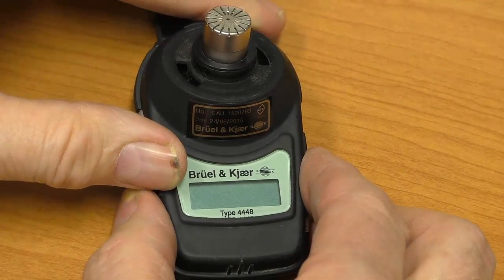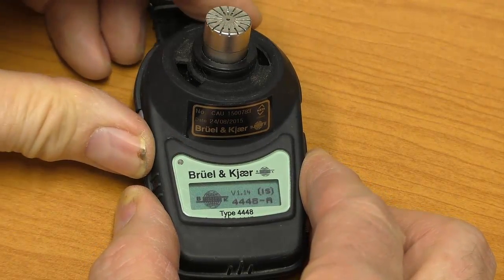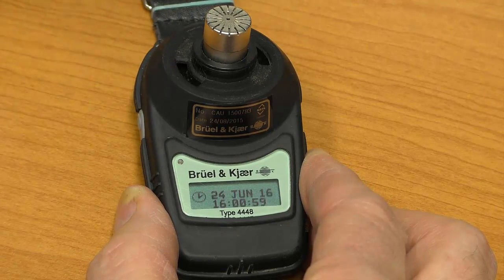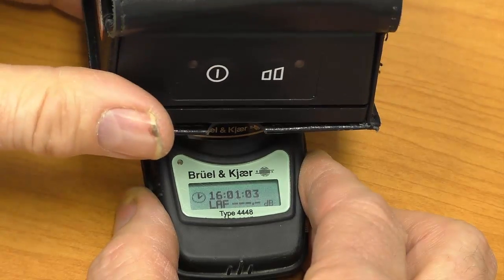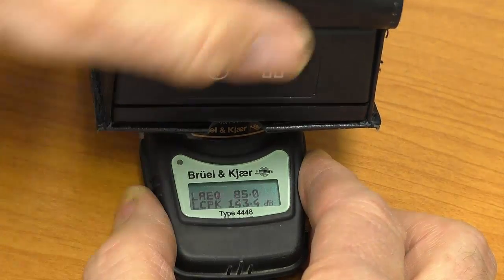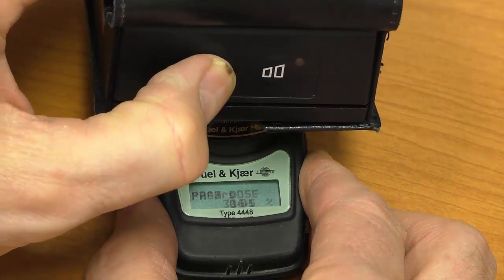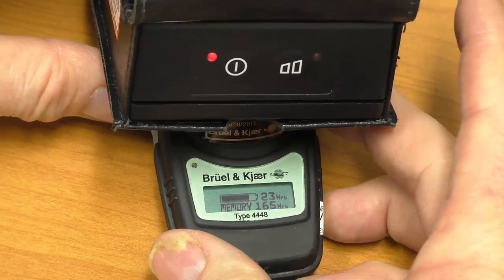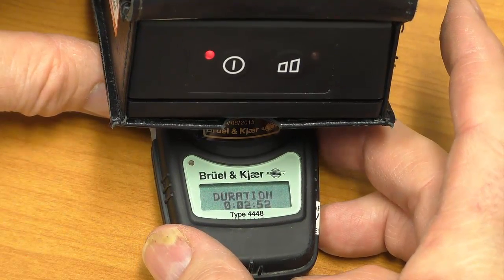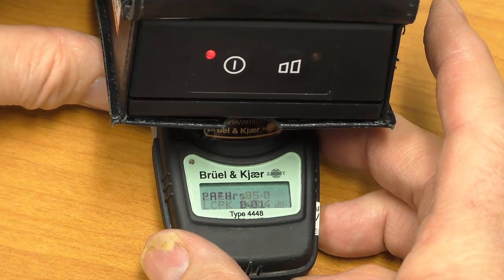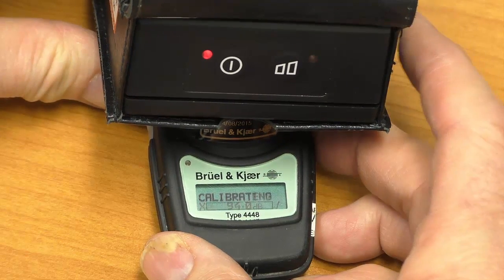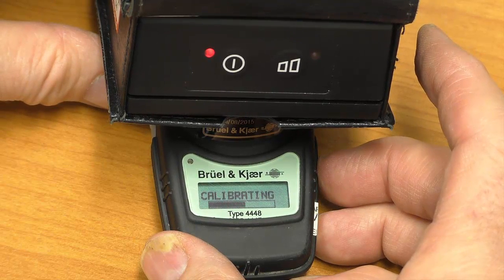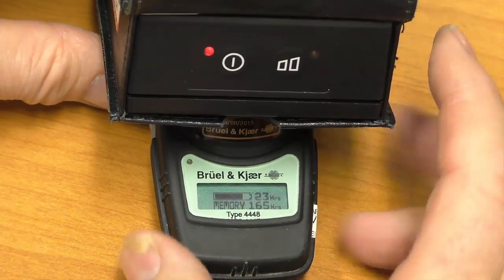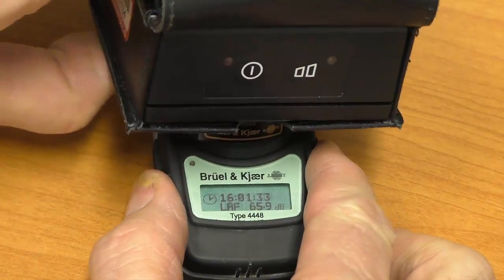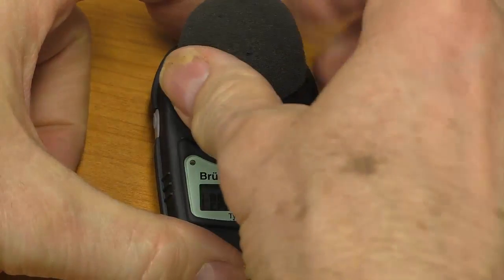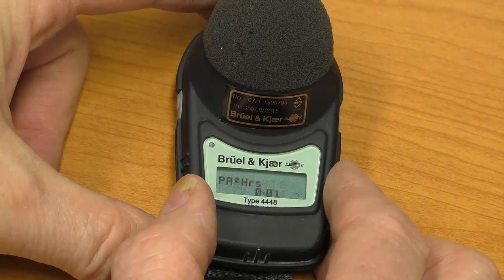The windshield must be on when the instrument is used. I'm going to turn the instrument on and have it boot up. Now I insert the calibrator on the instrument. It's sitting on the desk happily, fully inserted on the microphone. Now I turn the calibrator on, and in a couple of seconds the instrument will identify that the calibrator is on. Calibrate? Yes. It's calibrating. Cal OK. That's good. Now we can turn the calibrator off and replace the windshield. The instrument is now ready to be fitted.